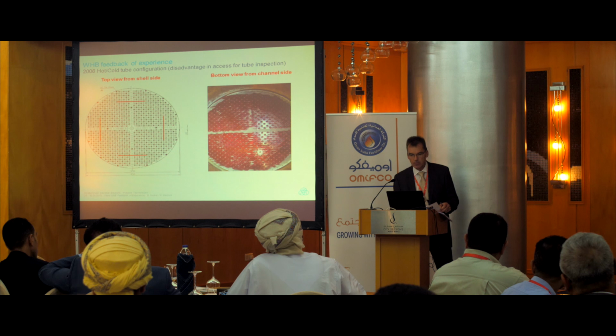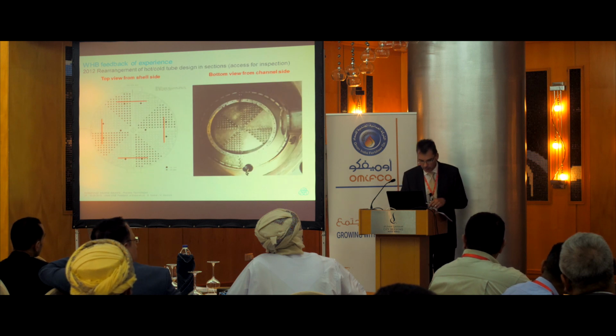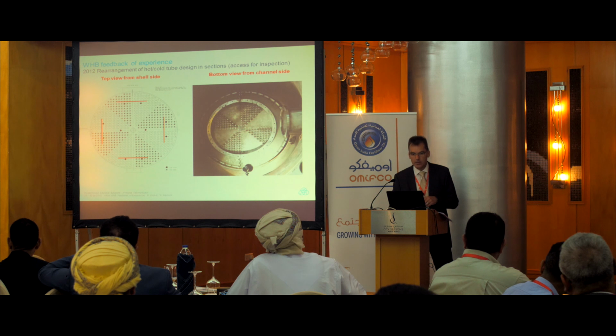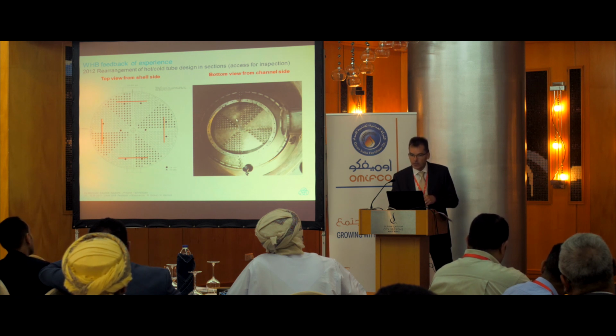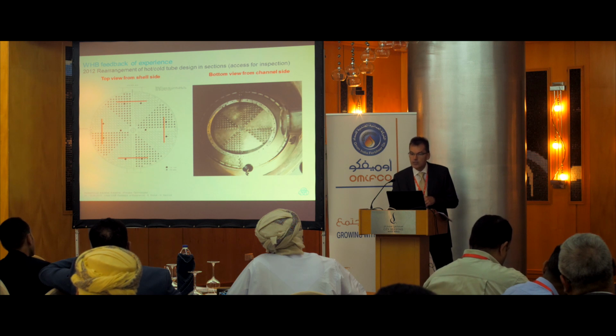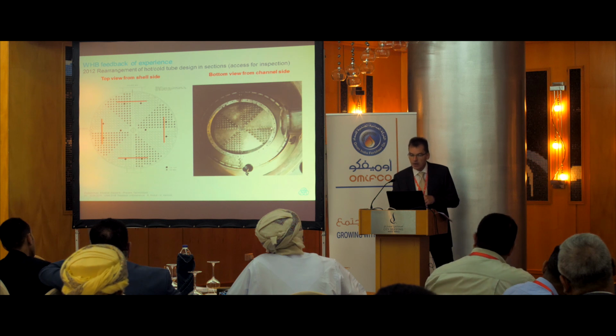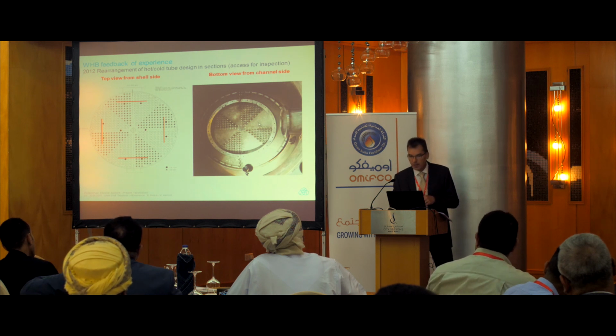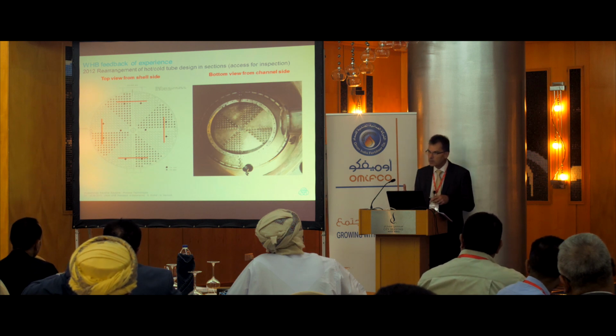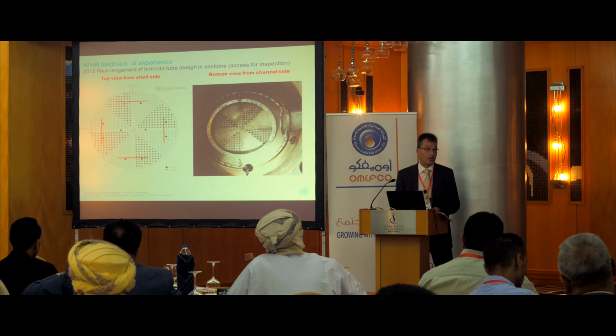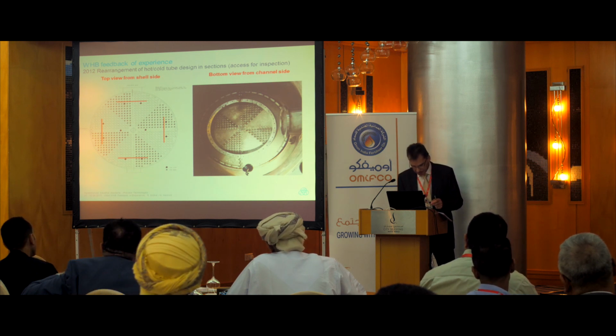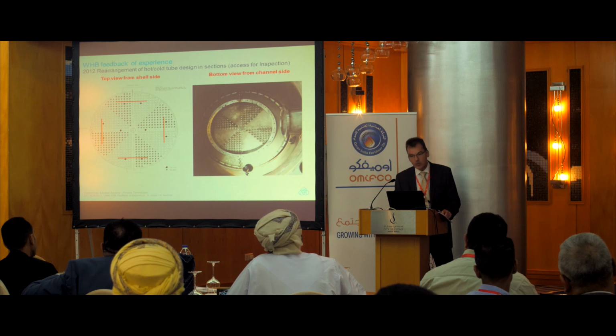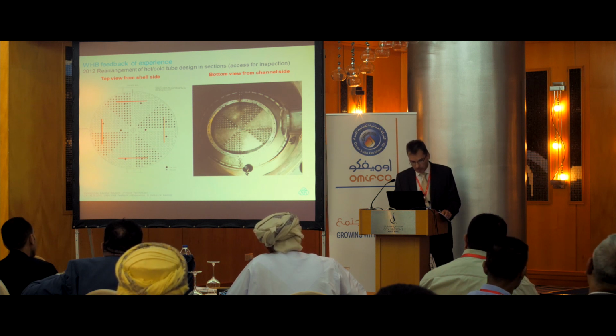Therefore, we changed slightly the design and said the tube configuration was basically kept the same. Look at the left side, but we invented here some covers on the false tube sheet. Underneath the covers are the ending of the hot-cold side, and we can remove these covers during inspection, and we can see the hot parts, which you see here clearly, and when you remove this cover, you can see also the cold parts, and you can identify then easier where is the leaking tube. Even during the hydro test, you see where is coming water out. Of course, we don't want to have leaks there, by the way. But there was another modification we did.